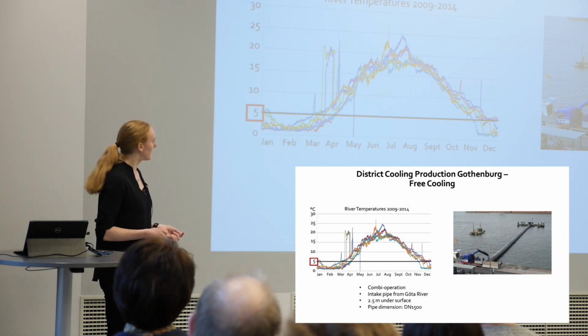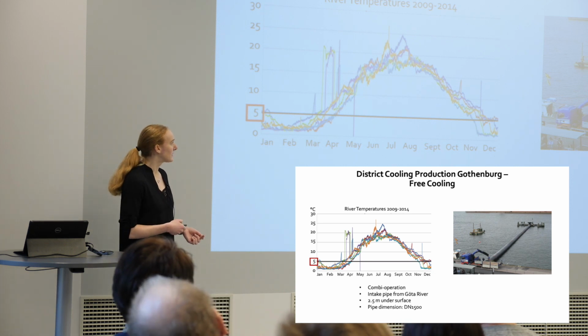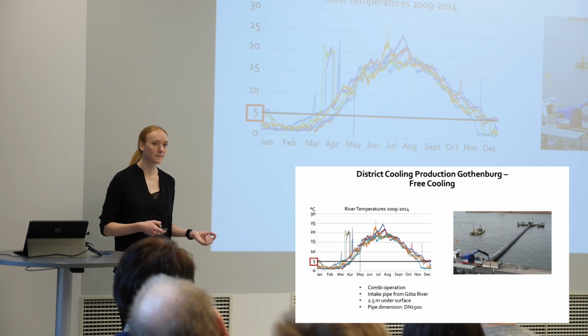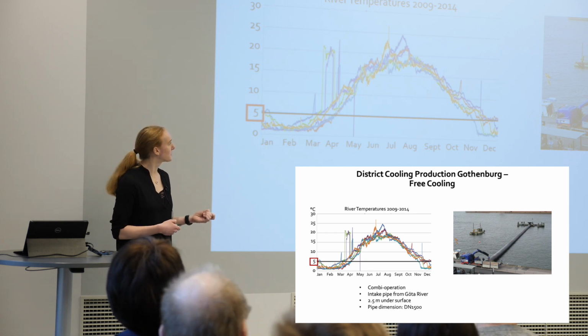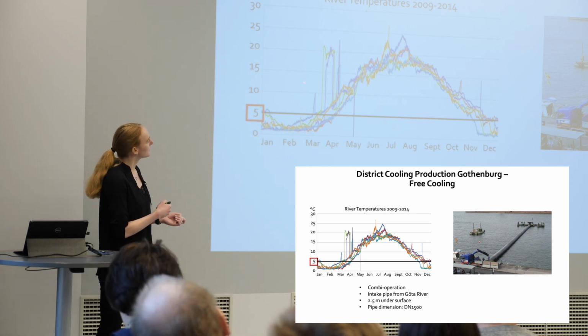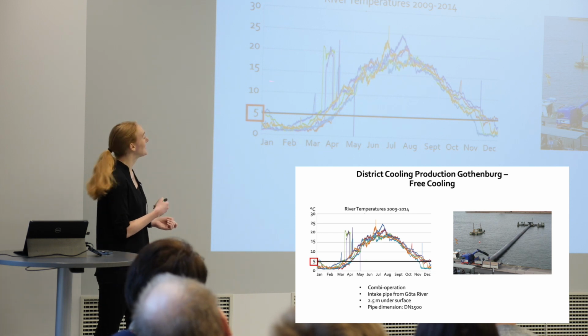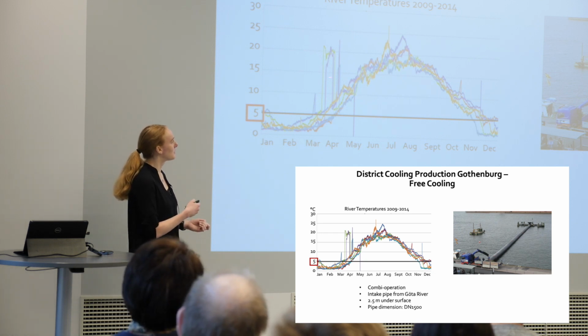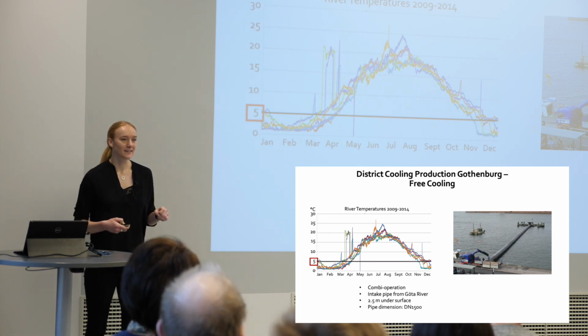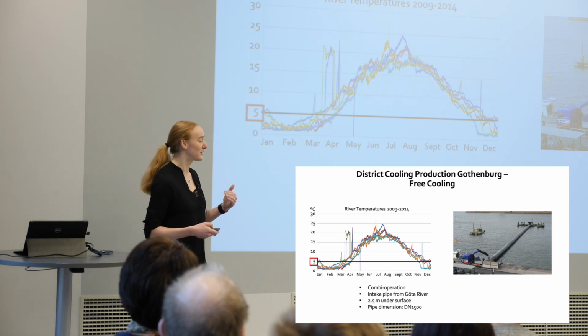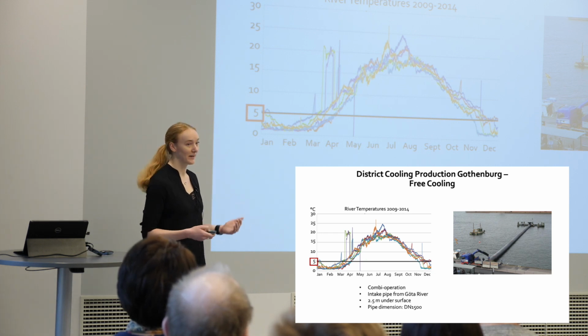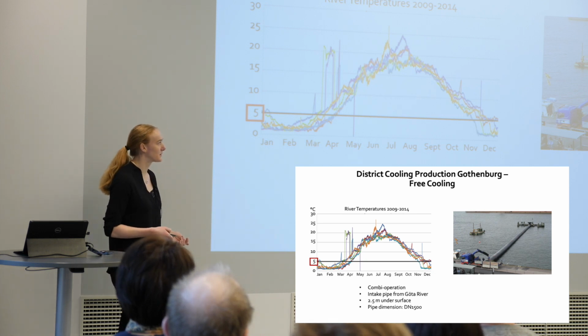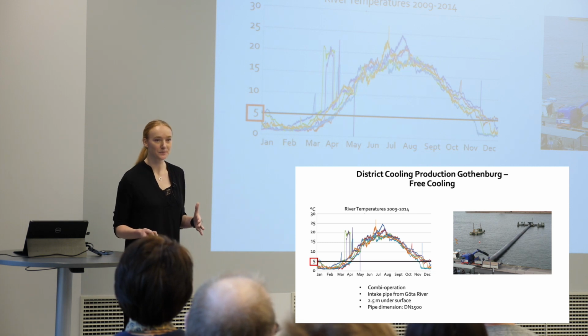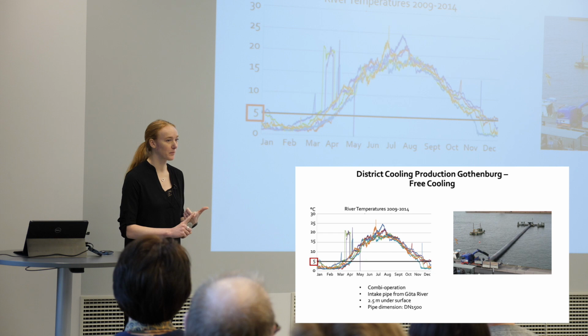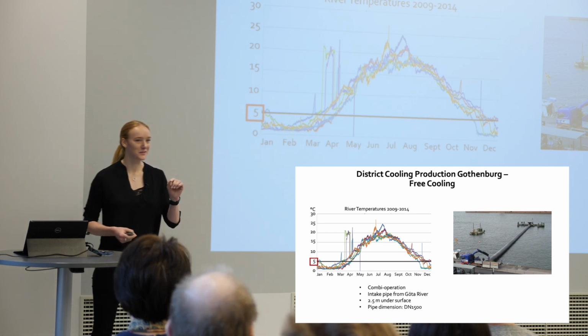And also, when the return temperature of the district cooling water in the network is lower than the river temperature, let's say it's 15, I will come back to this, the river pre-cools the returning chill water before it enters the chillers. And that is what's called the combi operation. So then the amount of free cooling that can be used, either 100% or in the combi operation, is dependent on what the return temperature of the district cooling system is. And so this you can remember for later on in the presentation.